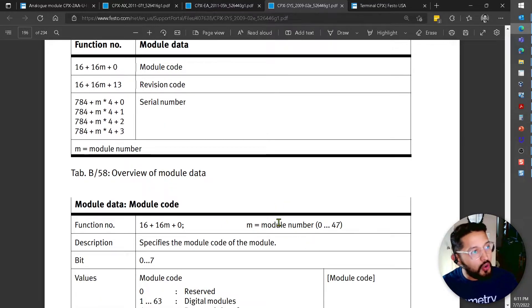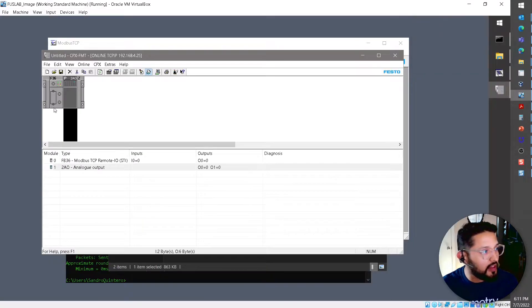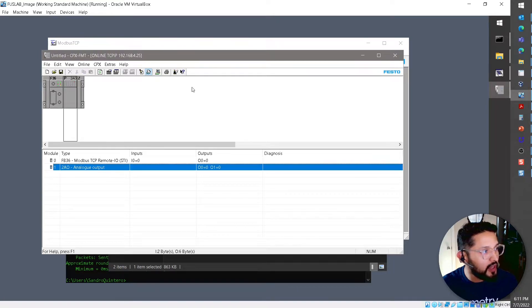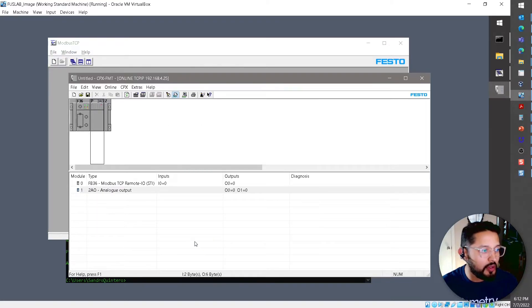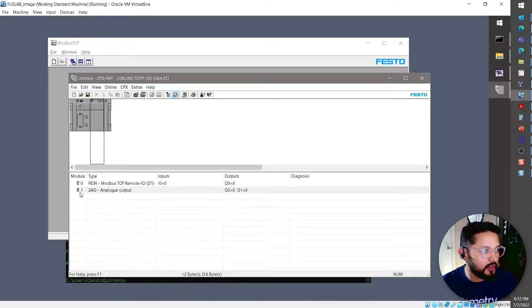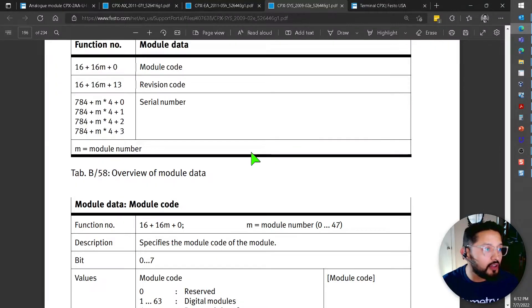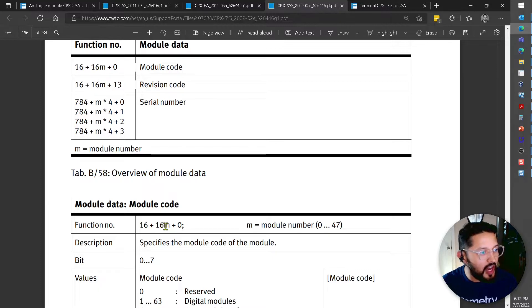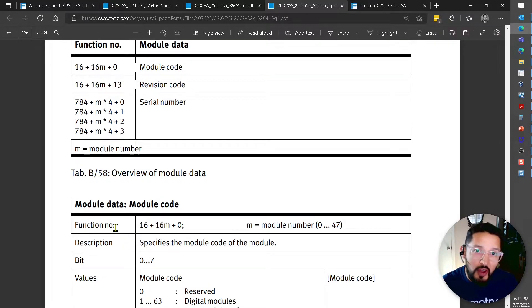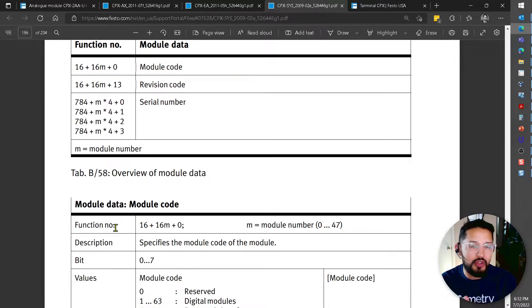The module code function number is calculated as: 16 + (16 × module_number) + 0. I want to read module number 1, so that's 16 + (16 × 1) = 32. You can verify this using the Festo CPX Maintenance Tool, where module one is at position 1. So the function number to read the module code of module 1 is 32.